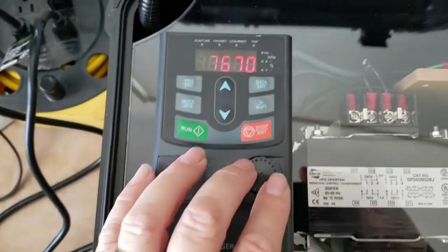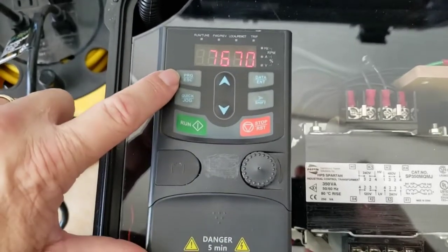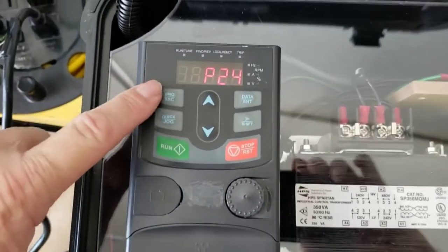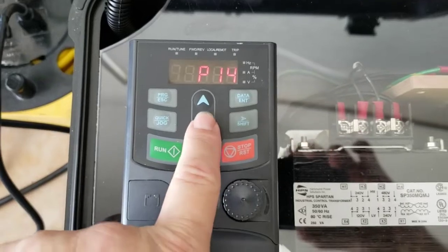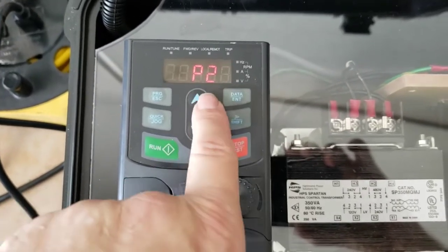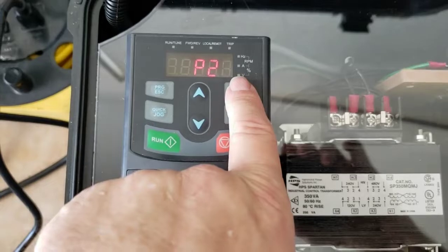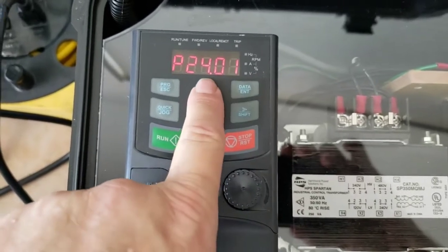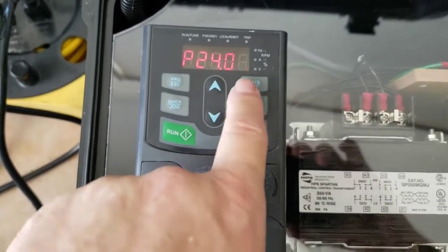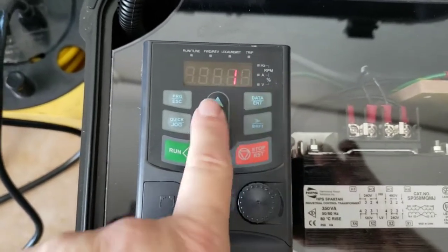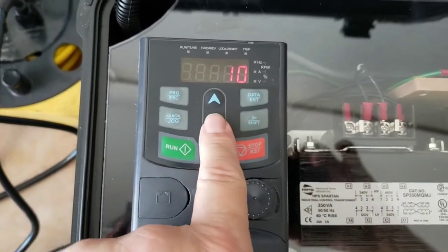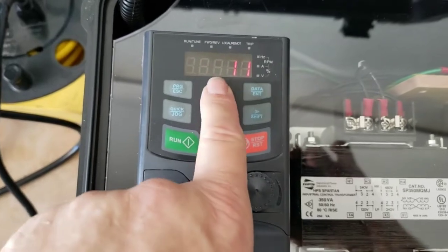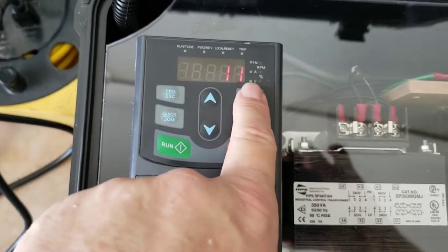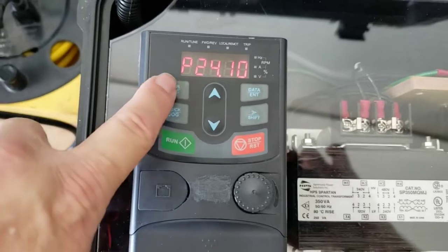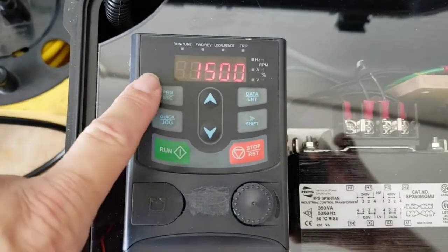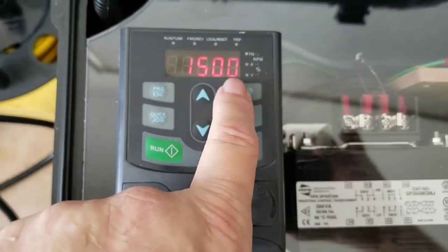Another thing you can do, if you need to, is push the escape button here, or program button, and go to menu P24. Use up and down, you can go through these. But if you go to P24, hit enter, this top right button, and then go to 09. So P24-09, hit enter. If you change to 10 as the normal value, you have two choices, 10 or 11. If I set this for 11 and then hit enter, and then hit escape a couple times to get back out of that, you can see I'm down to 1500 hertz.